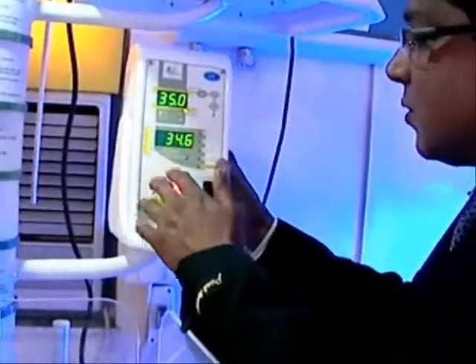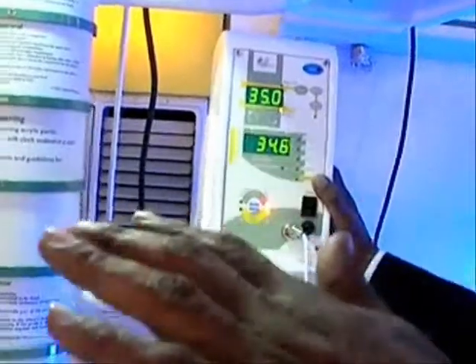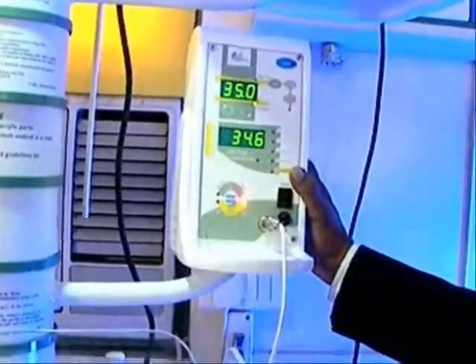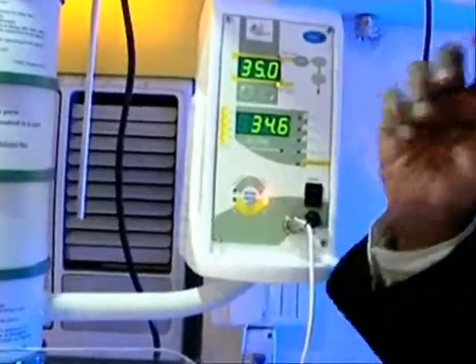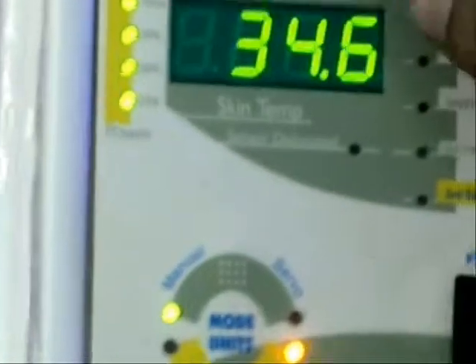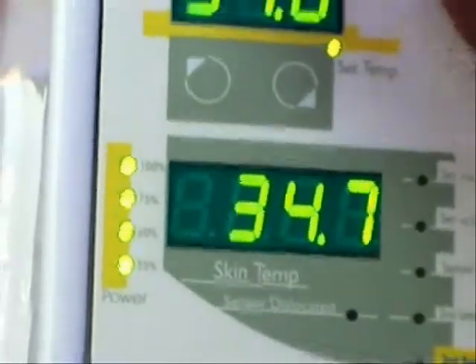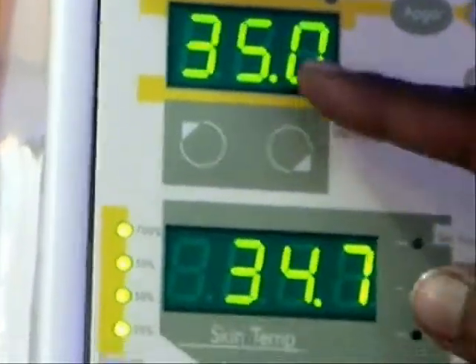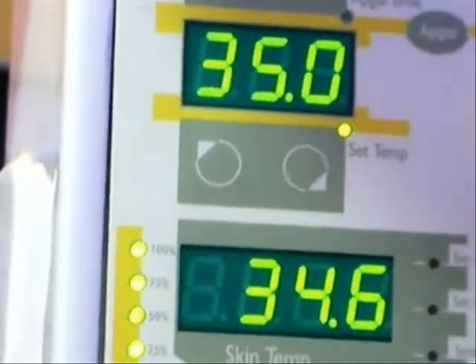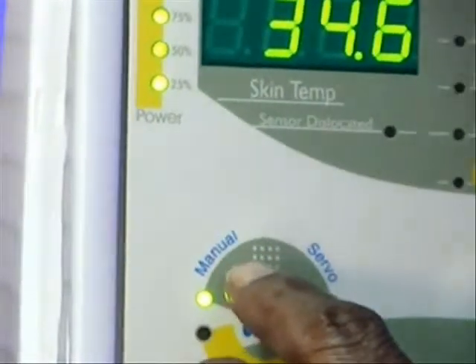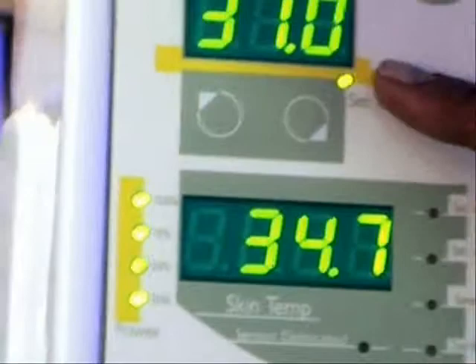Plus, you have another mode of control. You have either a manual mode or a servo mode. In case of an emergency, if you have to warm the baby very fast, just press this manual mode. Automatically, you can see the temperature set has now gone to 31 degrees centigrade. Initially it was on servo mode, I had set the temperature at 35, but once I press this manual mode, you can see the temperature has gone to 31 degrees.